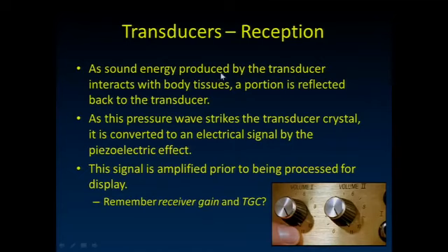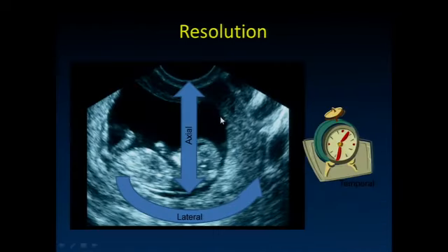All right, as the sound energy produced by the transducer interacts with those surfaces in the body and parts of it get reflected back, that strikes the face of the transducer, and that deformation of the piezoelectric crystal gets converted to an electric signal. That signal is amplified and processed for the display. Remember, we're amplifying it based on the depth it traveled, knowing that we have to compensate for the amount of tissue that the ultrasound beam might have traveled through.